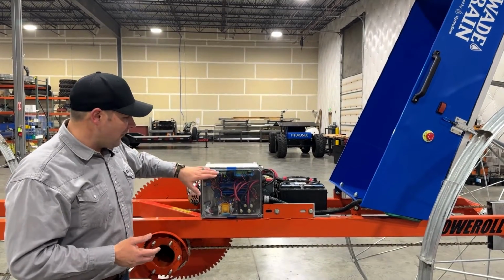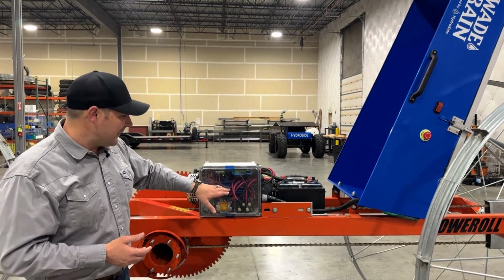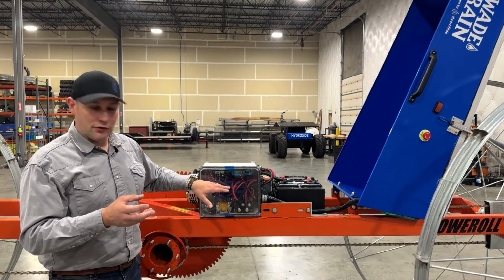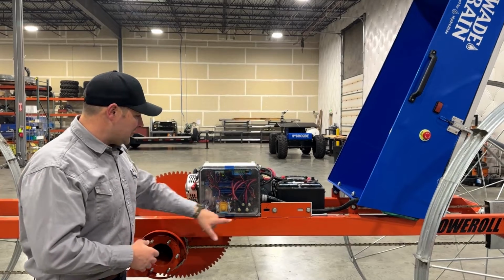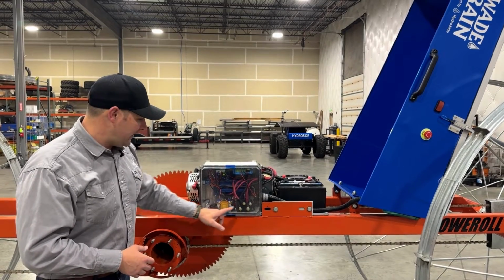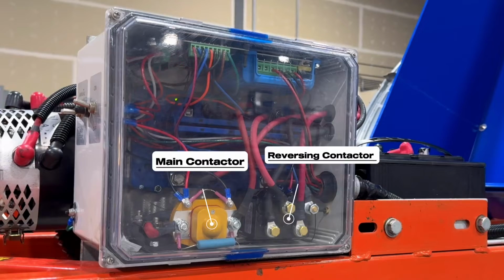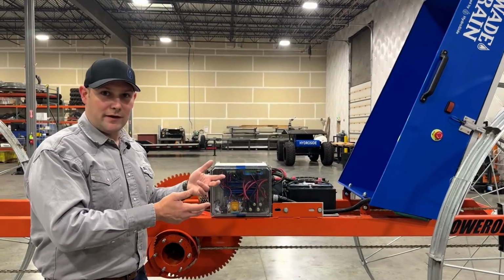Now, assuming we have a heartbeat, assuming that we have a motor controller with a solid green light, the next thing we'd want to check would be the connections in your main and reversing contactors. And if all of those appear to be at least solidly connected, then we'll move outside the box.